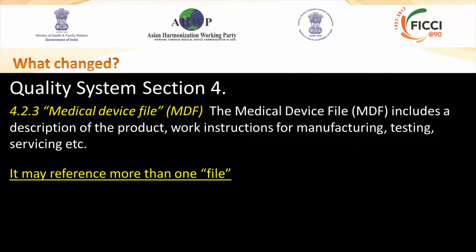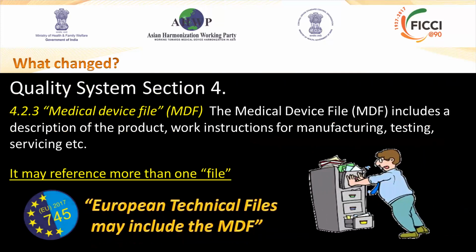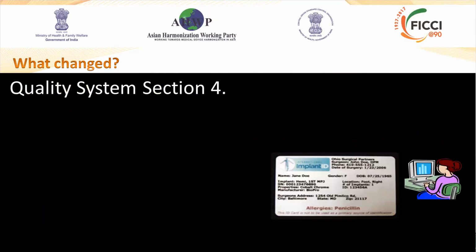There's also a new section called the medical device file, and it includes a description of the product, work instructions for manufacturing and testing. It can refer to more than one file. This is not unlike what we referred to sometimes as the European technical file. But that's an entirely new section within the standard.